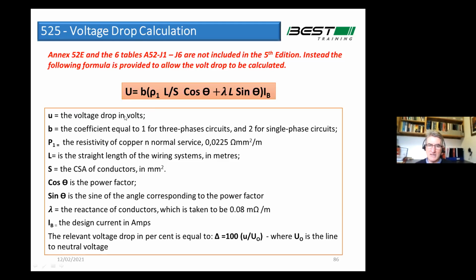Whether this factor here, B, should be 1, as they tell you in the wiring rules, or whether it should be 1.73. In my view, it should have been left at 1.73, and a lot of people agree with me. It would have avoided an awful lot of confusion. But just beware, if you do, which I've done and many people have done, I've put some figures into a spreadsheet and compared the results with the previous tables, and you'll find they're very, very close for single phase, but they're way off for 3-phase. And the reason they're off is because this factor says 1 instead of 1.73.